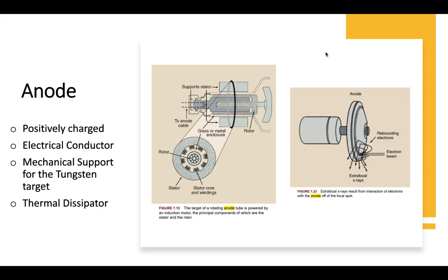The target is made out of tungsten and rhenium alloy with a layer of molybdenum and graphite under the tungsten target, which makes the anode lighter and easier to rotate. The target is angled. This design is known as the line focus principle. By angling the target, the effective area is much smaller than the actual area.